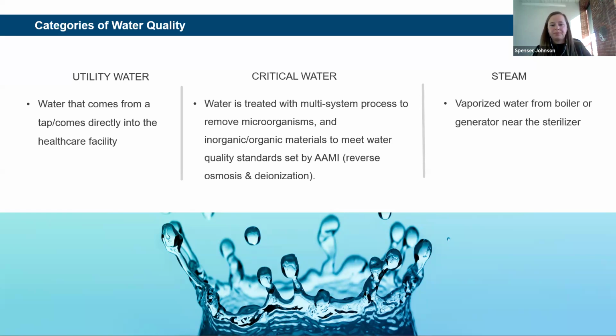What we've been recommending to facilities—we're in the beginning stages of this, this standard was released last year, but a lot of facilities are adopting it now. We're seeing facilities start to perform that risk assessment, add members of the central sterile department to their water management program, and perform the performance qualification testing to make sure they're in line with AAMI ST 108 requirements. Once you pass that, you move on to routine sampling, taking samples based on the frequencies defined in ST 108.